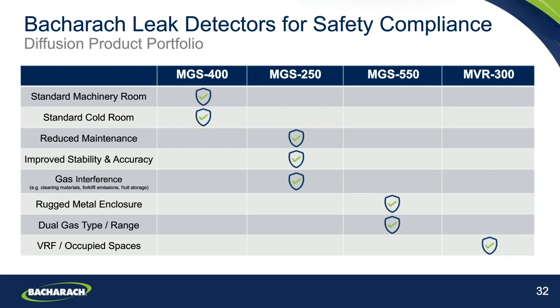The MGS-550 is really differentiated through having the ability of having two sensors there on one detector. That can be particularly useful, actually, coming back to the question on ammonia applications, to enable a single gas detector to have two sensors on there, one in that lower toxic range and one in the higher flammability type ranges, which can be placed in different locations by using remote sensor cables on there. There are also solutions out there for using in occupied spaces, such as hotel rooms, which typically will arise when VRF systems are used, which are growing in popularity around the globe. But our focus here will be what I guess we would define as the more standard machinery room and cold room type applications, chiller room applications, where the MGS-400 would be the most straightforward and applicable solution.